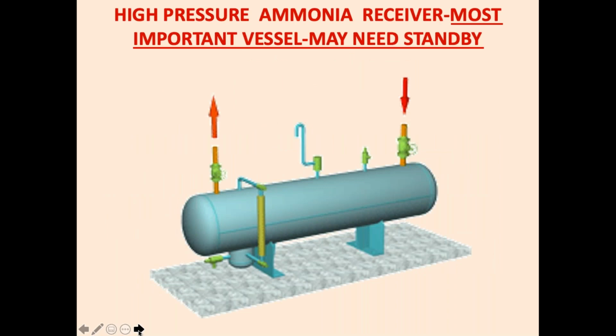The most important vessel in any ammonia refrigeration plant is the ammonia receiver because it stores the entire quantity of ammonia in a system. And many times a standby is essential or recommended, because in case of problems with the main plant, you should be able to pump down ammonia somewhere in the system instead of releasing it to atmosphere. Normally, this is what we suggest: provide a standby receiver, or two receivers of 50%, or three receivers, two of 50% and one 50% standby. Depends upon the criticality of the plant, but you can design according to that.